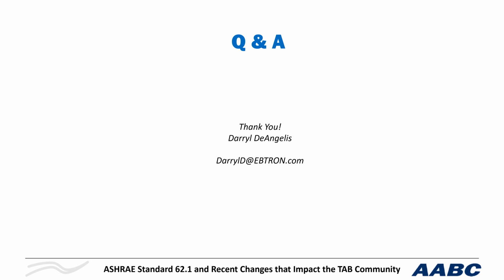All right, and next question. Should outdoor air sensor inspection and ventilation verification be more frequent? It certainly will depend on the systems. Some systems may require less maintenance. One of the things the standard refers to is to look at the O&M manual, which would have the manufacturer's recommendations for calibration. Anything with a pressure transducer, as I mentioned, is going to drift. Thermal sensors don't drift. They're a lot more stable with respect to that.